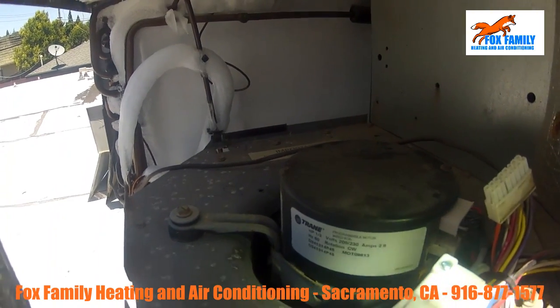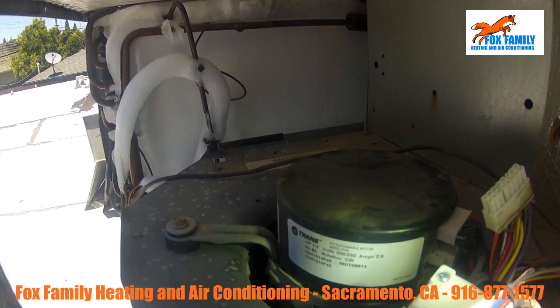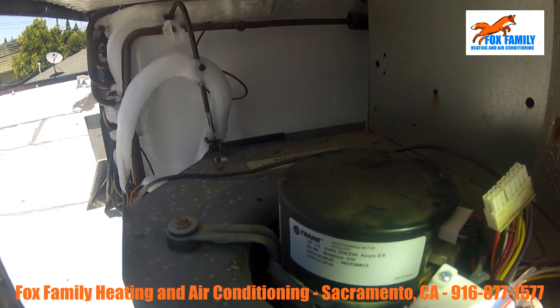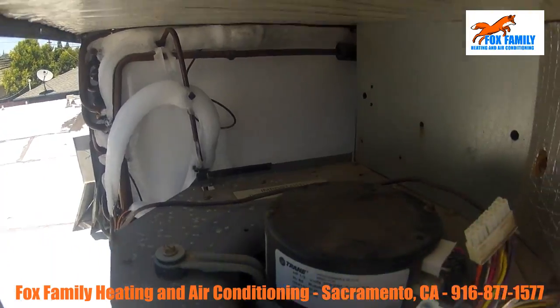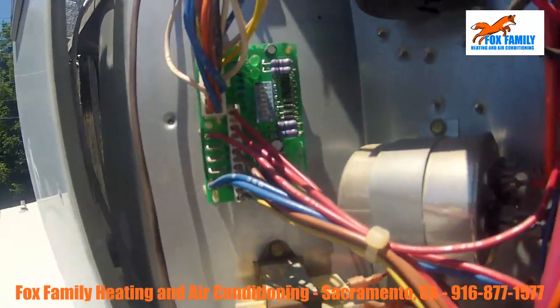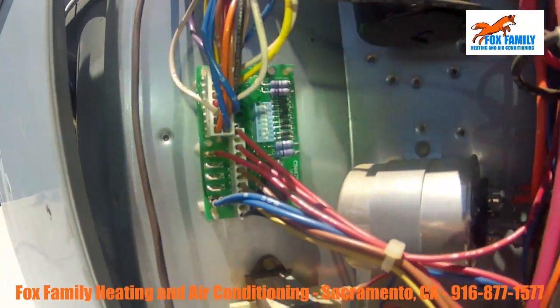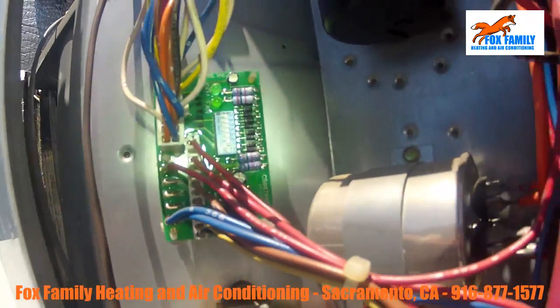So if you hook your Tech Inspect up to the motor and it starts running, then you know that your problem is not with the motor, it's somewhere back here. So this is what controls the motor. This is likely our problem. They just had a power surge not too long ago here, so we're going to start looking here.